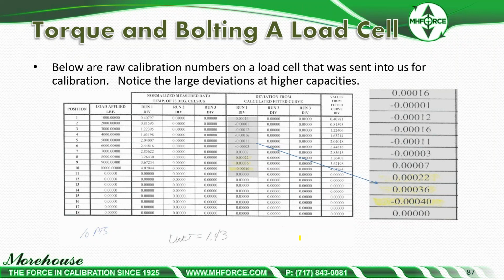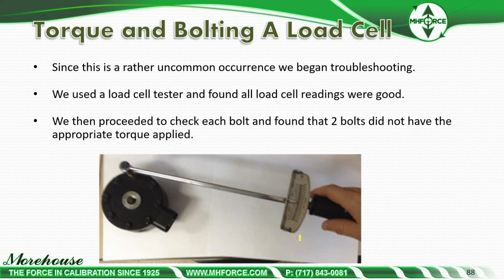Torque and bolting a load cell. Here's a situation. We ran a load cell, saw the deviations were rather high, and started questioning it. It was higher than what we expected. What we did is we took one of these torque wrenches here, rather uncommon. Now we do it all the time, it's one of our troubleshooting techniques. We used a load cell tester. Everything's good. Everything's positive on the load cell. All good. We proceeded to check each bolt and found that 2 bolts did not have the appropriate torque applied.